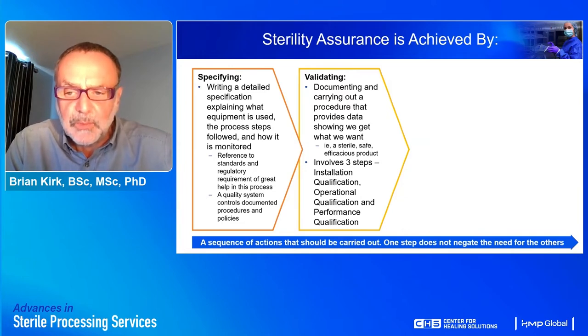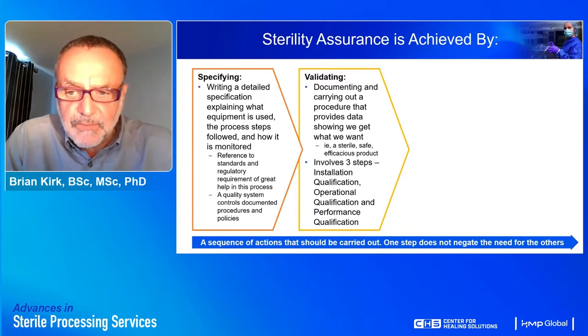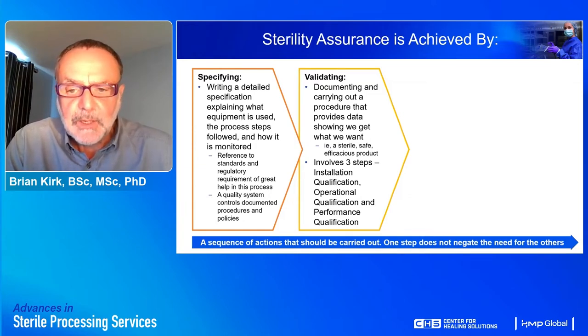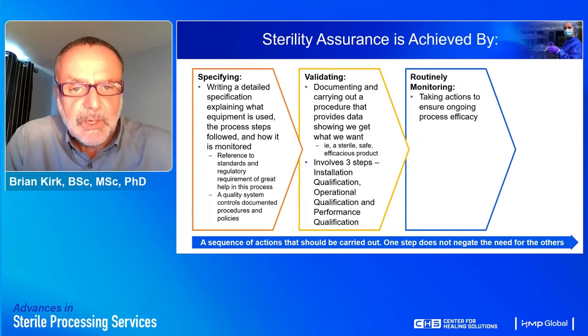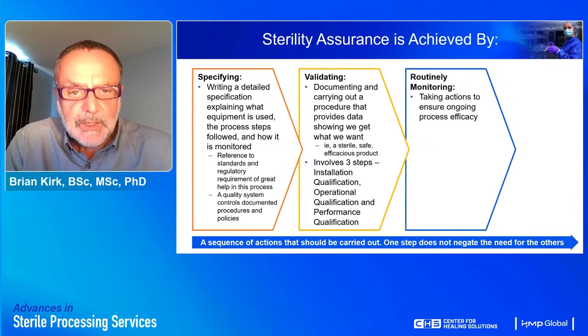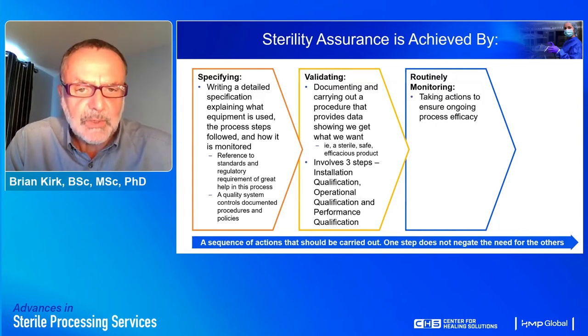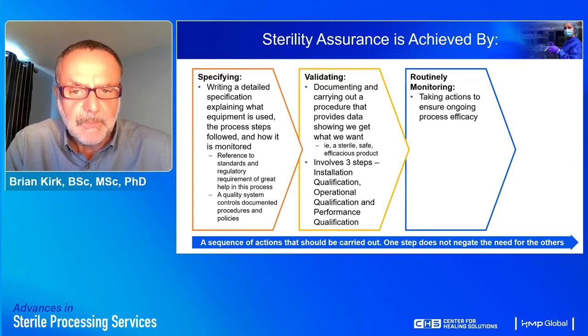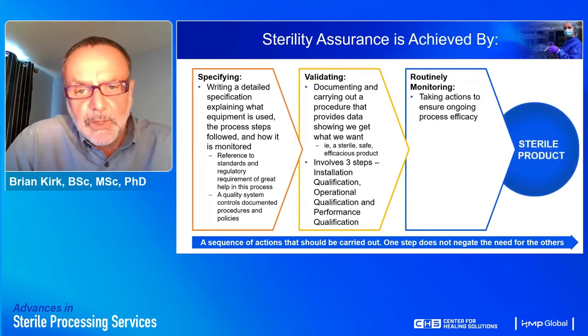In some areas of the world, performance qualification is also called product testing, but it aims to establish that the processing cycles used in a sterile processing department (SPD) can sterilize the loading configurations the SPD wants to use. We must also take measures to routinely monitor the sterilization process, since sterilization processes are quite complex and can be regarded as unique events. Having validated our process, we must ensure every cycle still falls within required specifications — if we get all this right, we will end up with a sterile product.